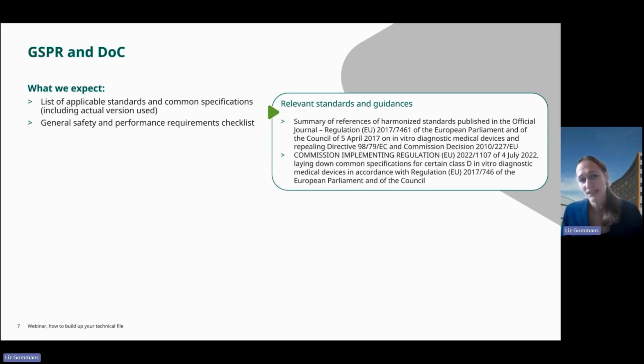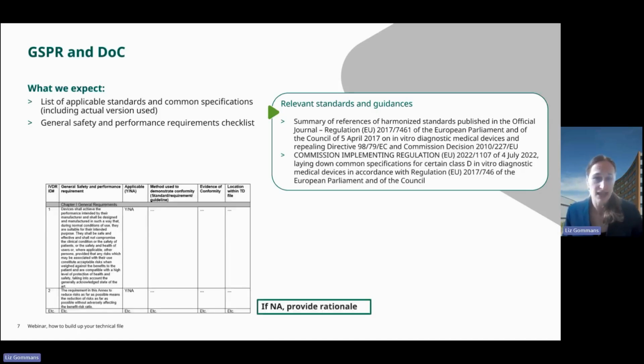So yeah, what do we expect here? For the GSPRs, we expect a list of applicable standards and common specifications, including the actual version used, so including the years, and then also the GSPR checklist. So here we have an example of a GSPR checklist.